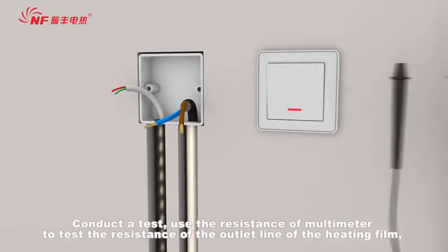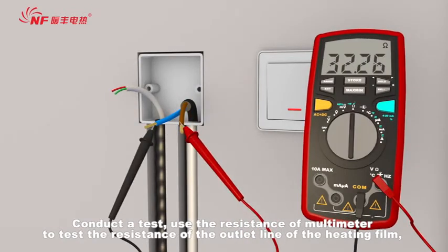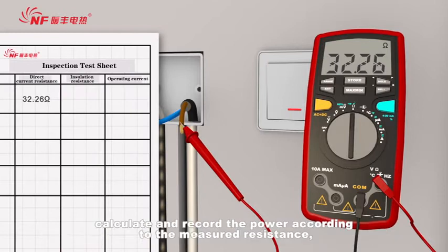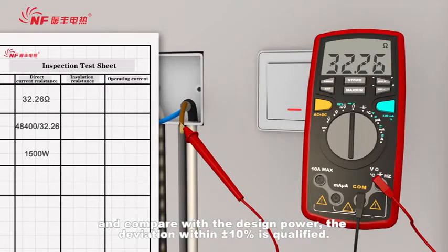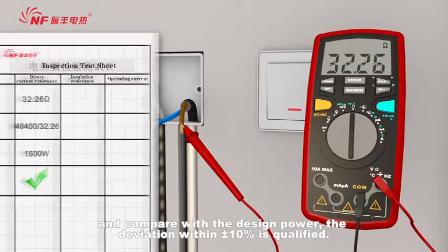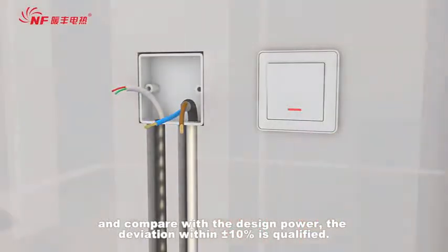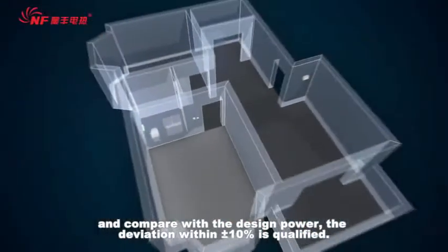Use the resistance of multimeter to test the resistance of the outlet line of the heating film. Calculate and record the power according to the measured resistance and compare with the design power. The deviation within plus or minus 10% is qualified.